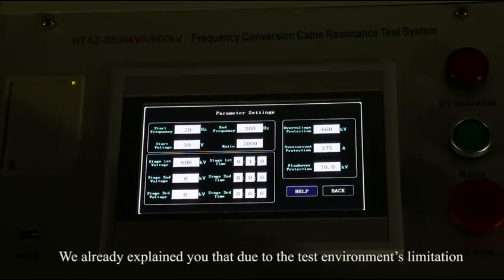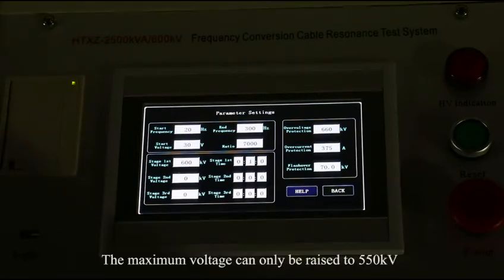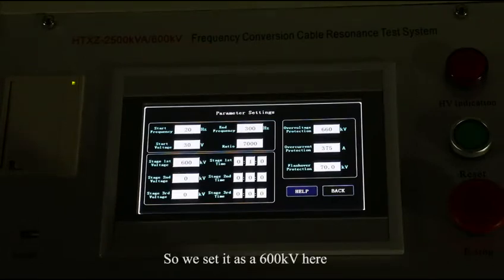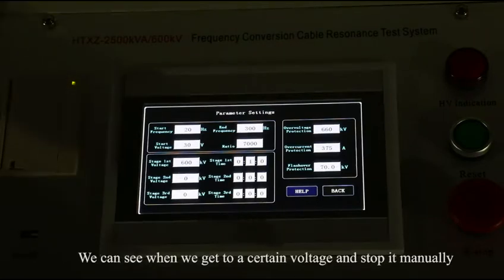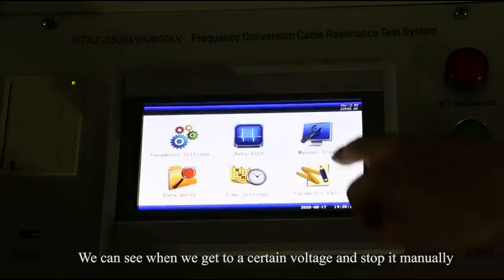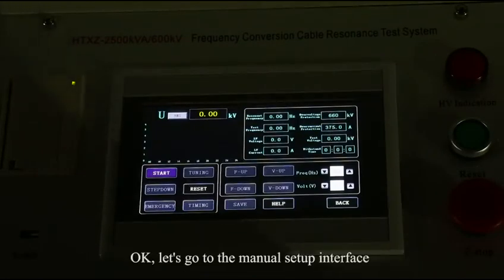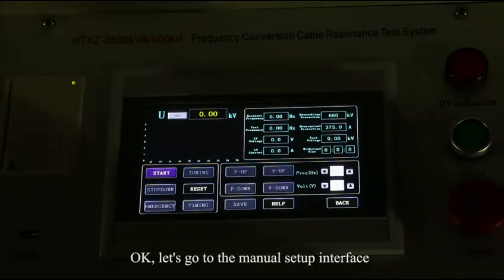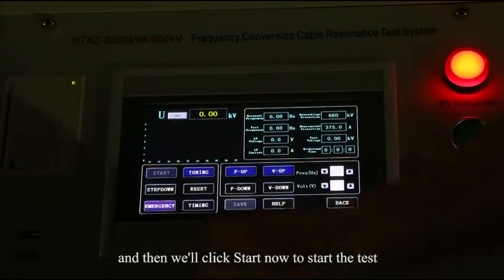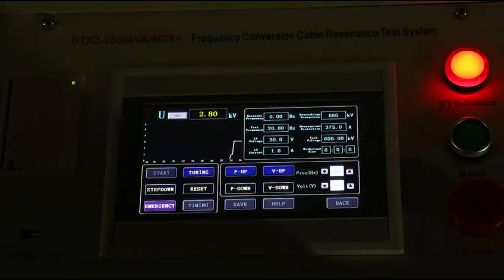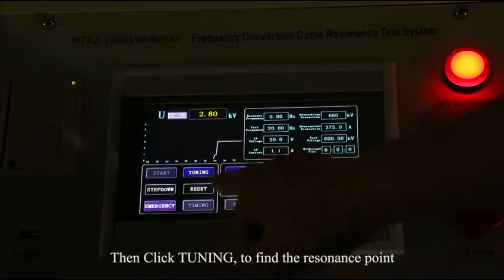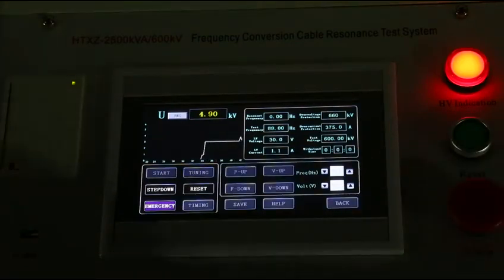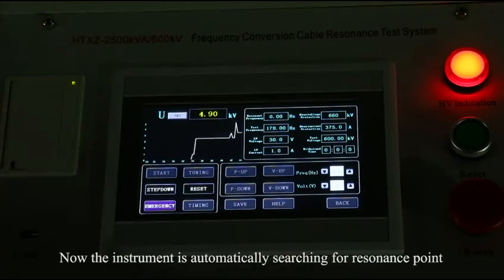We already explained to you that due to the test environment's limitation, the maximum voltage can only be raised to 550 kV. So we set it as 600 kV here. We can see when we get to a certain voltage and stop it manually. Okay, let's go to the manual setup interface. And then we will click Start Now to start the test. Then click Tuning to find the resonance point. Now, the instrument is automatically searching for resonance points.